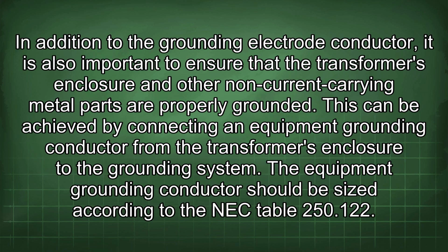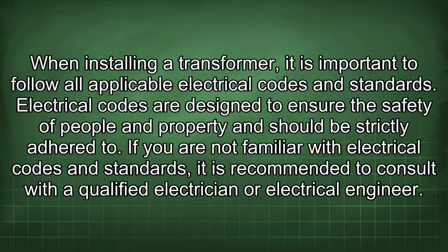In addition to the grounding electrode conductor, it is also important to ensure that the transformer's enclosure and other non-current carrying metal parts are properly grounded. This can be achieved by connecting an equipment grounding conductor from the transformer's enclosure to the grounding system. The equipment grounding conductor should be sized according to the NEC table 250.122. When installing a transformer, it is important to follow all applicable electrical codes and standards.